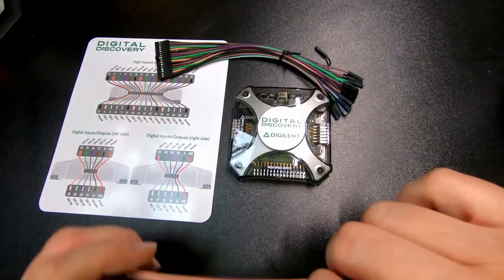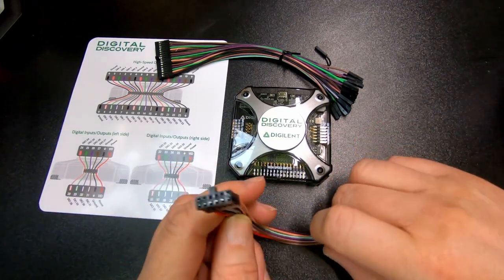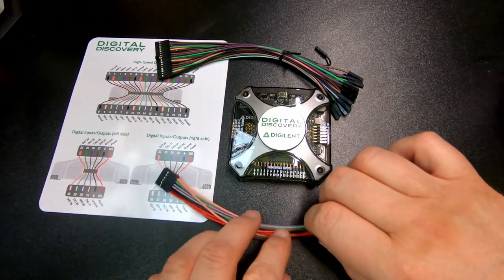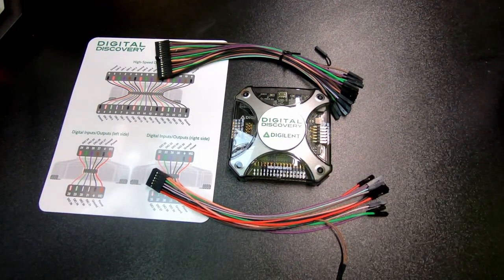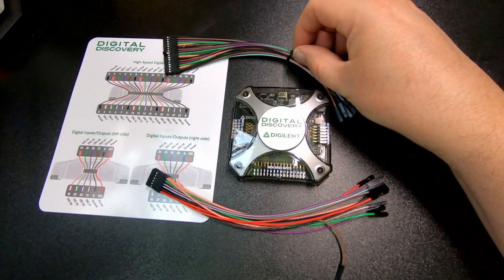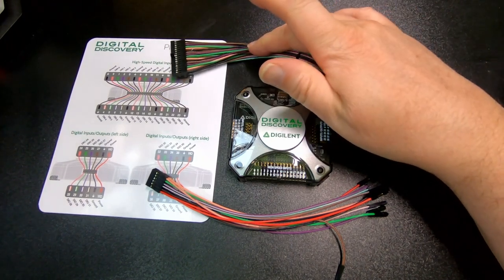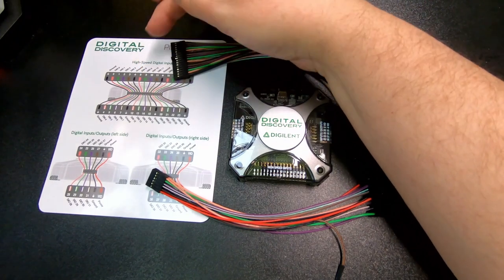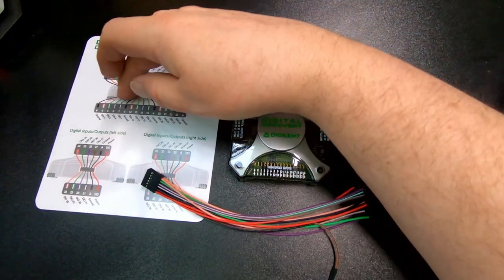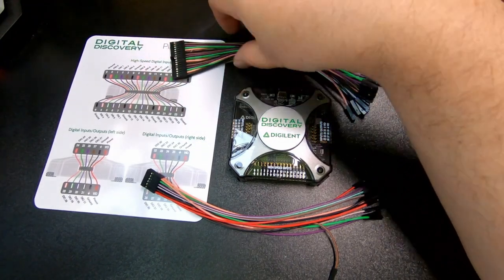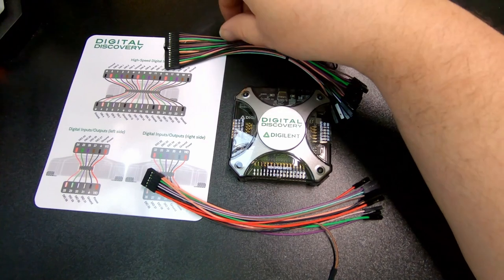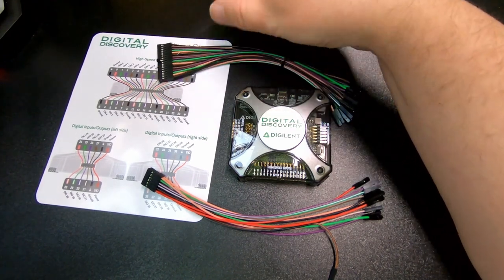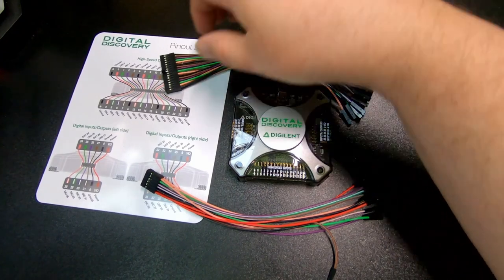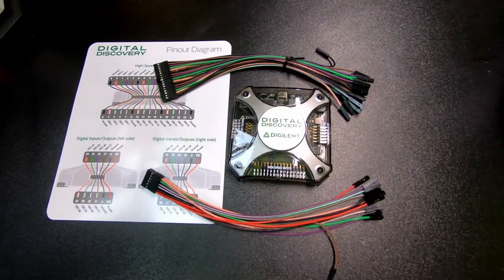And that's for the big connector. I don't know what the logic is, we're only providing for one side, but that's the way it's provided as a standard set. But there is one connector type which they call a high speed connector adapter. I haven't really got good pictures of it, it's like a PCB that connects into here, and then it has twisted pair cables individually per input. It's more dedicated for when you're hitting the limits of the speed of this thing, then you get better signal feed into the device.